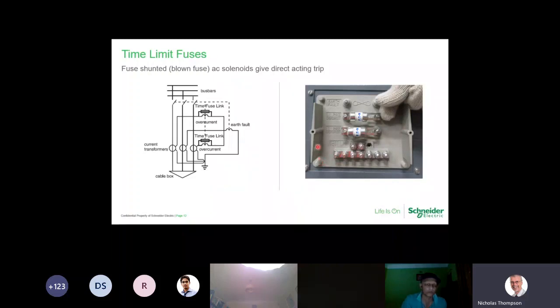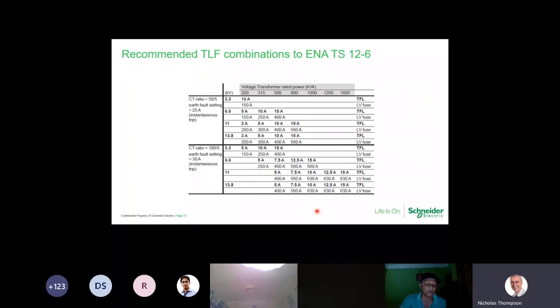So that's what it will look like in practice. Very simple fuses, very simple to change, and the only way you're going to know if it's blown is by the circuit breaker being tripped and the trip flag on the front of the ring main unit.